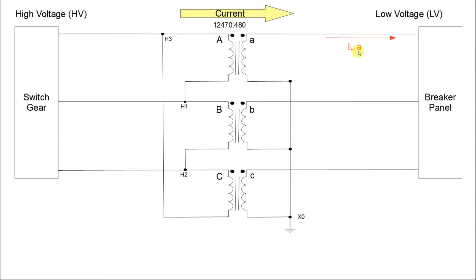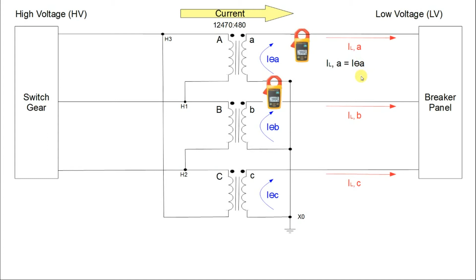Now let's think about this. If I take my Fluke 3000 and measure this secondary phase A line current, and then measure my phase current here, are they going to be equal? Is there any branch circuit here, anywhere for current to flow other than through each meter? There is not. So I can say my line current for the secondary A line is equal to my phase current for the A secondary phase.